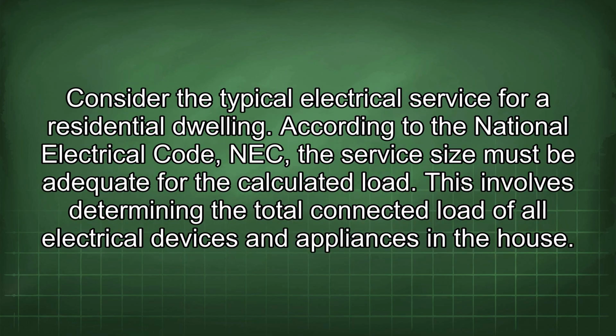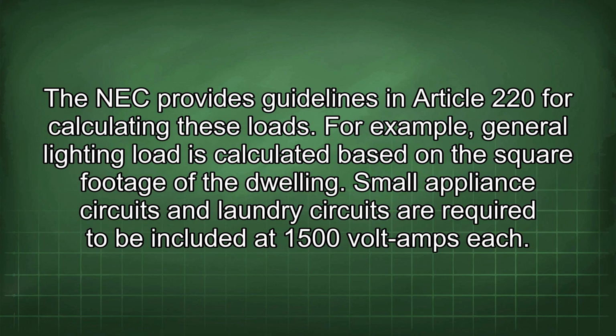Consider the typical electrical service for a residential dwelling. According to the National Electrical Code, NEC, the service size must be adequate for the calculated load. This involves determining the total connected load of all electrical devices and appliances in a house. The NEC provides guidelines in Article 220 for calculating these loads.